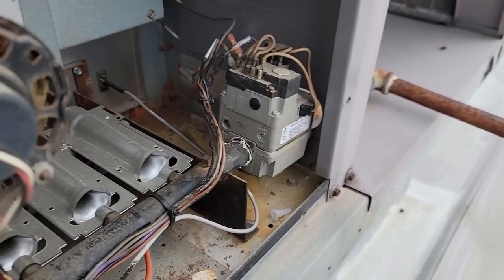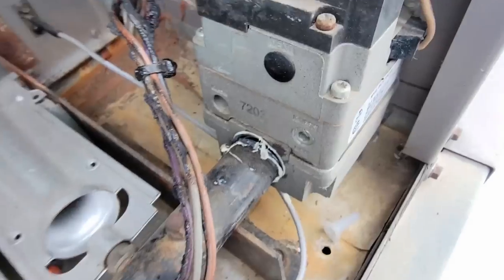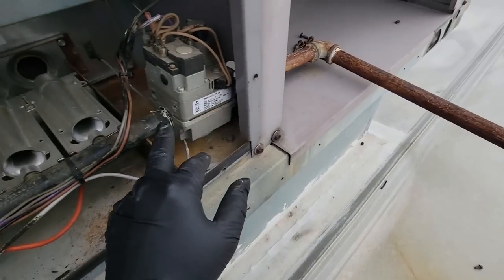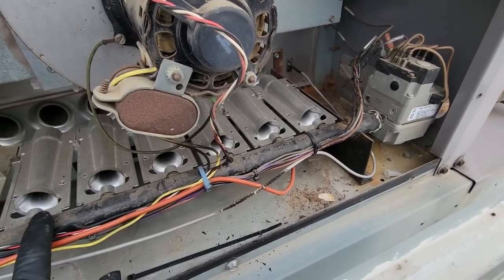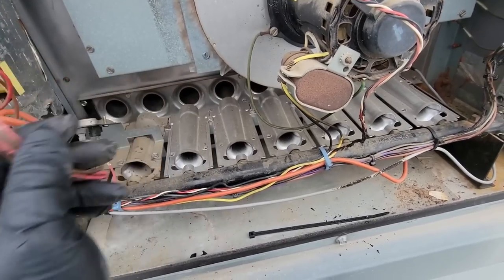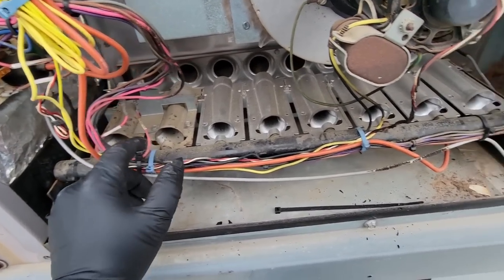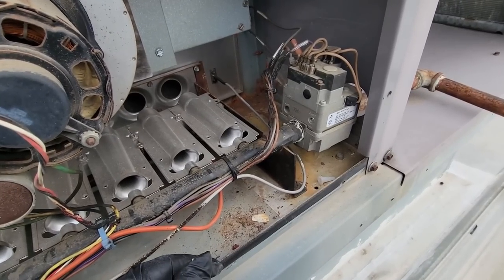It's just not looking good. Looks like there might be a plug missing — let me get a closer look. Something happened — it looks like it was supported on the roof somehow and got shoved down, and that broke. I'm going to have to try to take this apart and see if we can get it re-threaded at the shop. I don't know if we have enough room to get on there with anything. This is a catastrophic mess and I cannot believe they put a rollout switch that is self-resetting — that's just stupid.